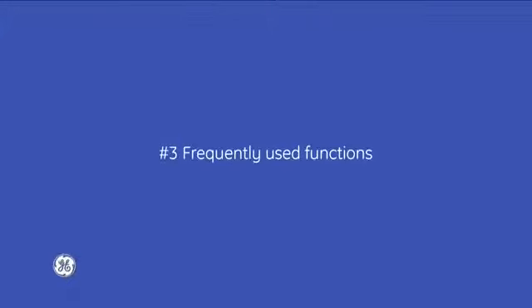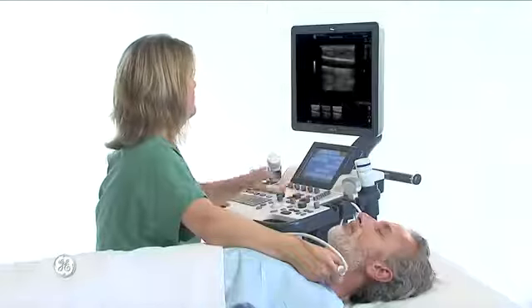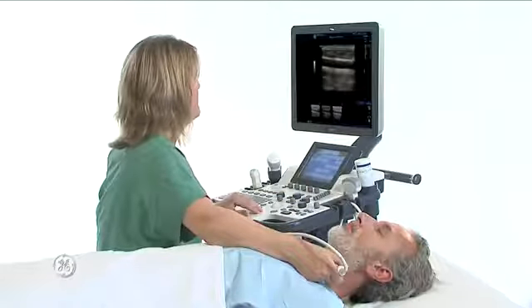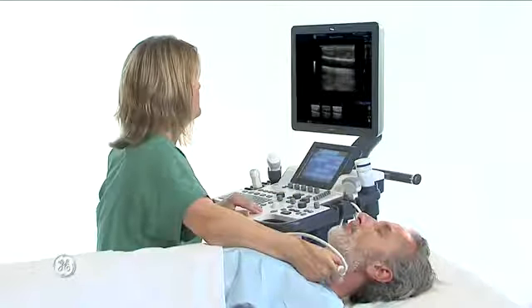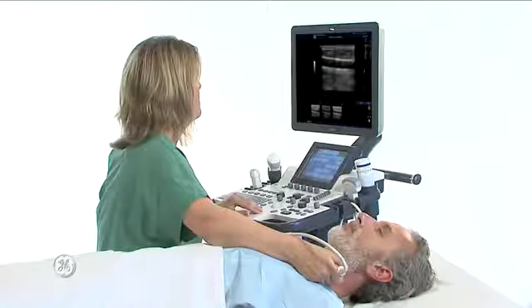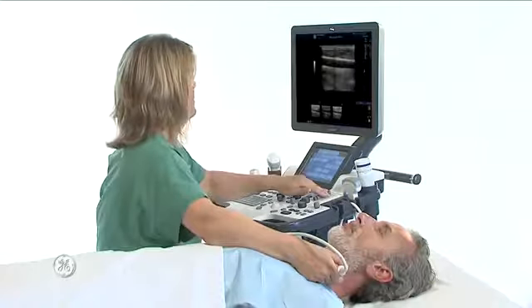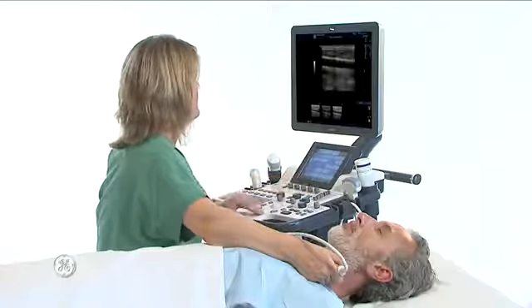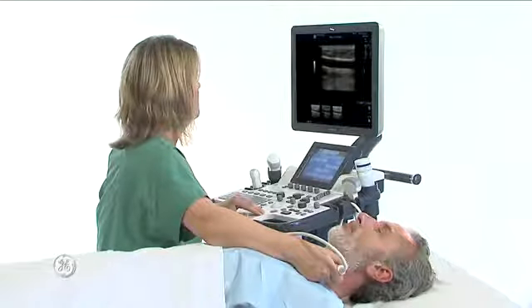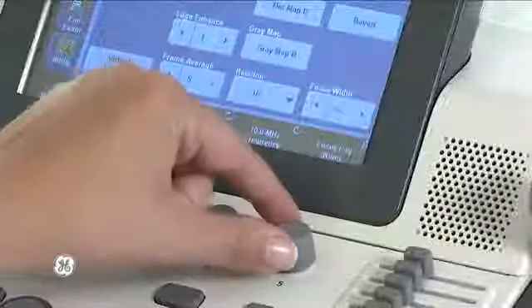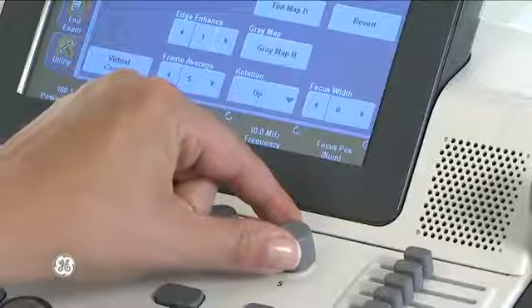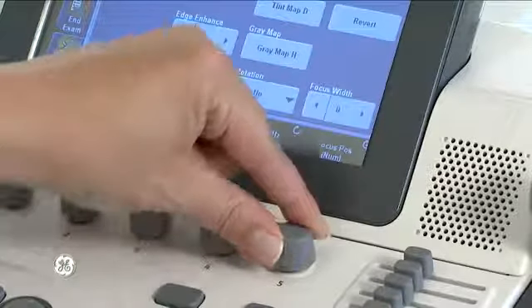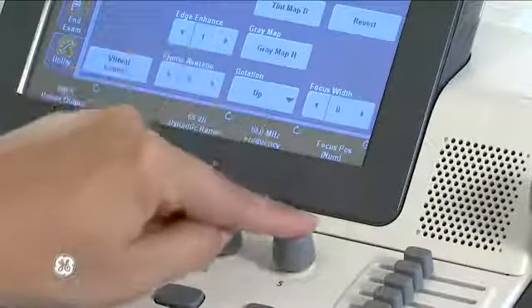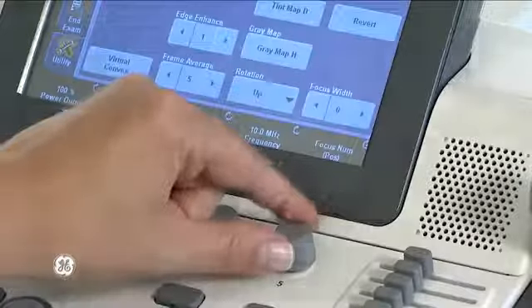Part 3. Frequently used functions. Focus increases the number of focal zones, moves focal zones, or changes zone width so you can tighten up the imaging beam to a specific area. Place at lower half of display depth or below organ of interest. The focus control can be found on the touch panel knob 5. Rotate the knob to change the position of the focus and press or push the knob to activate the number of focal zones.